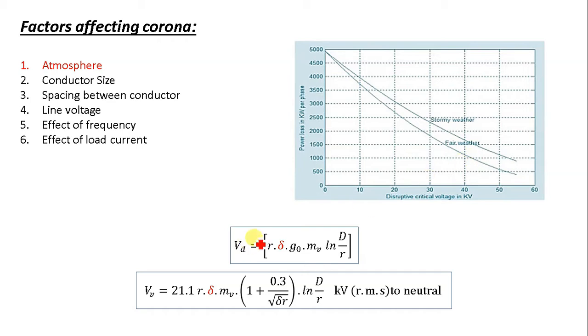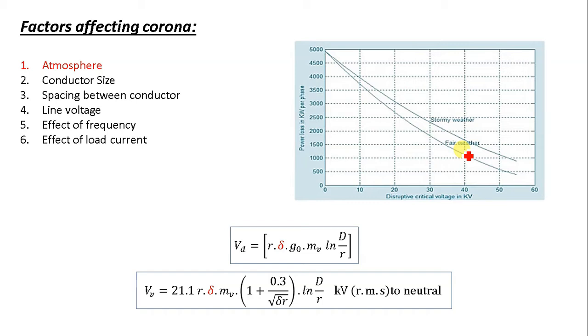Delta, which is a function of temperature and pressure, will be different in different seasons. In monsoon season, Vd will be lesser because the amount of moisture in air is greater, so ionization happens at a very low voltage compared to fair weather. In stormy weather, corona occurs at very low voltage, and atmospheric condition affects both corona and corona loss.